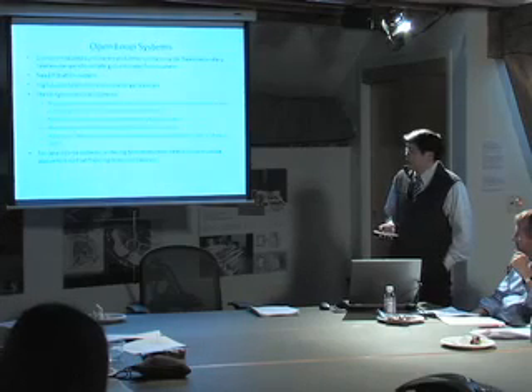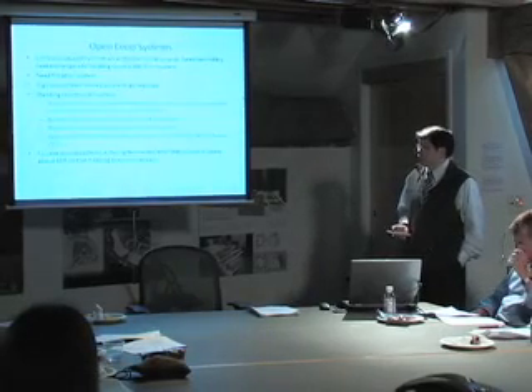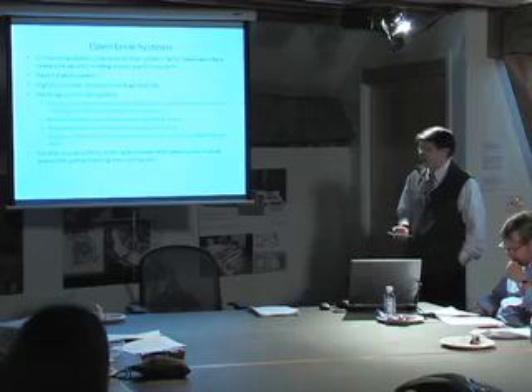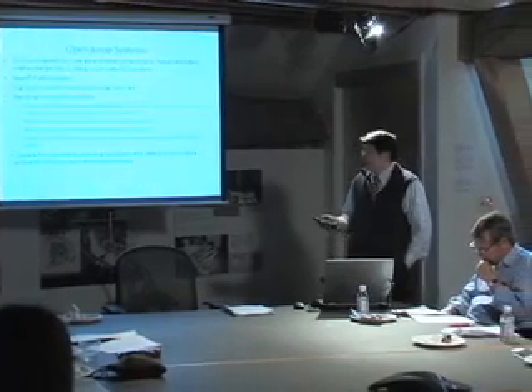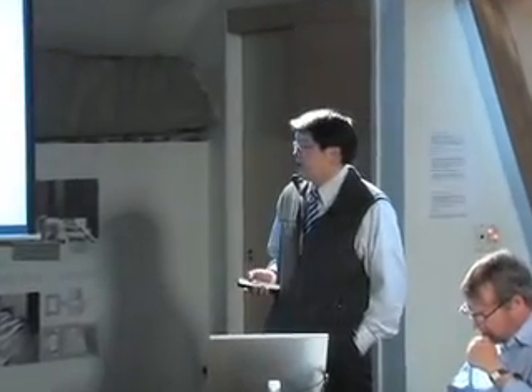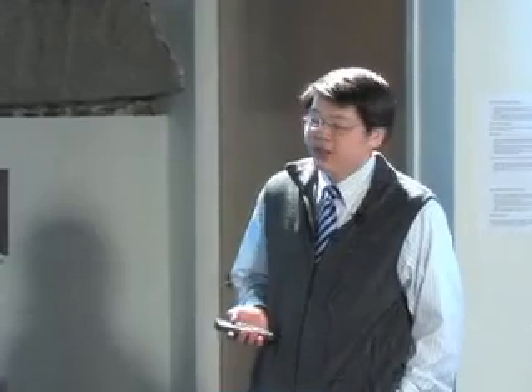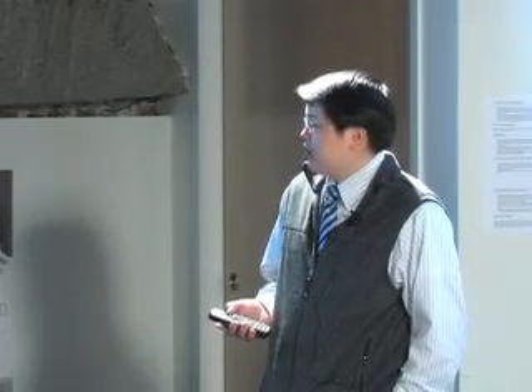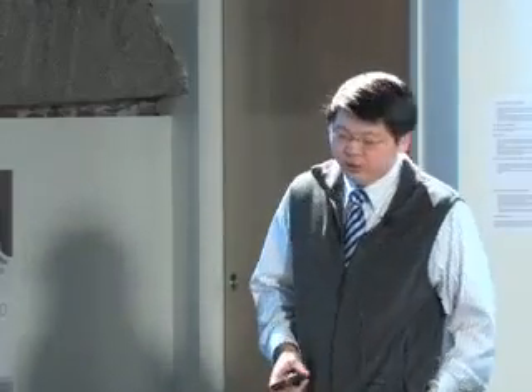You need to obtain the permit from a local sewer or stormwater authority, or from EPA if you want to discharge to a surface water body. You need to file an underground UIC, underground injection control, registration, for which you have to do water testing and lab analysis. If you have to drill in a wetland, you have to get the permit from the local conservation commission. You may check out these guidelines for geothermal systems from the Mass Department of Environmental Protection. They revised it in August last year. For lake systems, one of the issues is that the water body has to be big enough to handle the load. If the lake is not big enough, during heating season the water may get too cold and may cause freezing in the heat pumps.